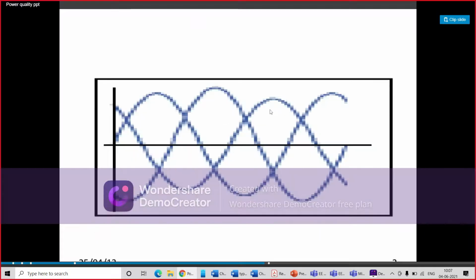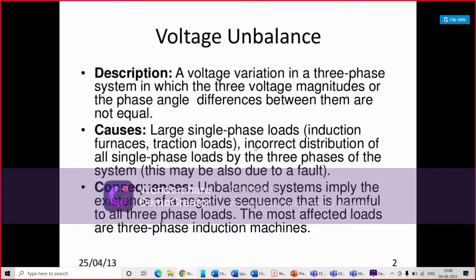Then you have voltage unbalance. You can see from this figure, this is the normal voltage and suddenly, in this particular phase only, these two phases are okay, but this third phase is going down, so you can say that the three phases are not balanced. What causes it? Large single phase loads, and incorrect distribution of single phase loads among the three phases of the system. And what are the consequences? An unbalanced system implies the existence of a negative sequence that is harmful to all three phase loads.